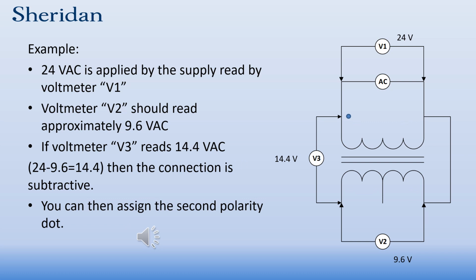Let's look at another example. We apply the same 24 volts AC, and we read the same 9.6 volts at the secondary. But if we read voltmeter V3, what we see is it's the difference between the two voltages, 14.4 volts. This means that they're being connected in series, of opposite polarity connection, and you assign your second polarity dot and then assign terminal designations or terminal tags as seen here in this illustration.